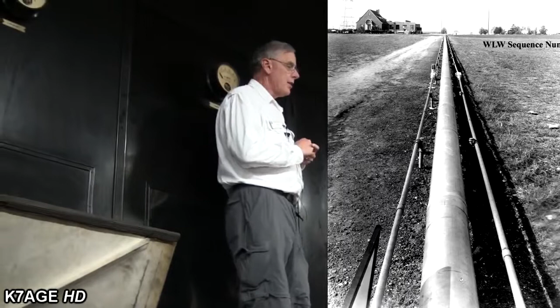There were 2 modulators, and 2 separate modulation transformers, so they were completely independent, and they could route those - run them in parallel, or route them individually to a single amplifier or pairs of amplifiers. The modulator was capable of about 180 kilowatts of RMS power per modulator, so that'd be 360 total. It takes roughly 50% of the carrier power to 100% modulate the transmitter.